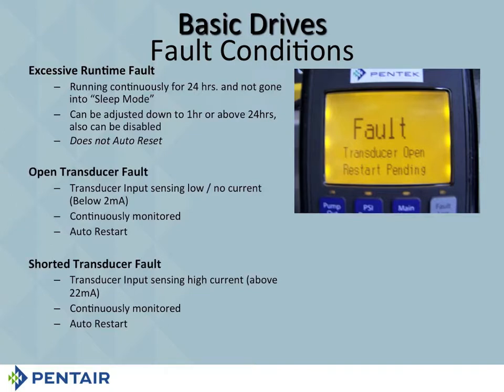Open transducer or shorted transducer. Again, these are auto restart. These are 2, however, that I'm not necessarily going to wait for. It's not like the voltage ones, okay? They will restart if the problem fixes itself. But if you've got an open transducer, there's a possibility it's not going to fix itself. So you need to find that out. Or if you've got a shorted transducer, you need to find that out so you can fix it.